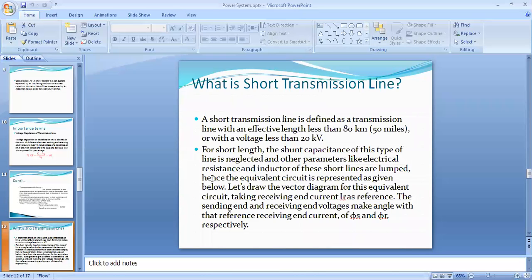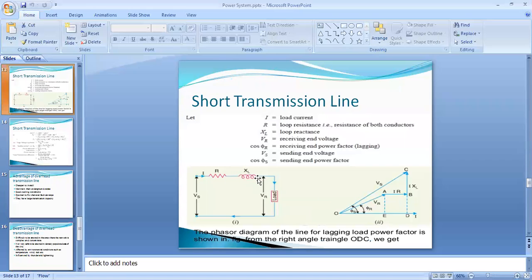What is a short transmission line? A short transmission line has an effective length less than 80 km and voltage less than 20 kV. For short transmission lines, the shunt capacitance is neglected and only resistance and inductance are considered. In the circuit, R and XL are connected in series with a load. The sending-end voltage is Vs, the receiving-end voltage is Vr, I is the load current, R is the loop resistance, XL is the loop reactance, and cos φr is the receiving-end power factor.